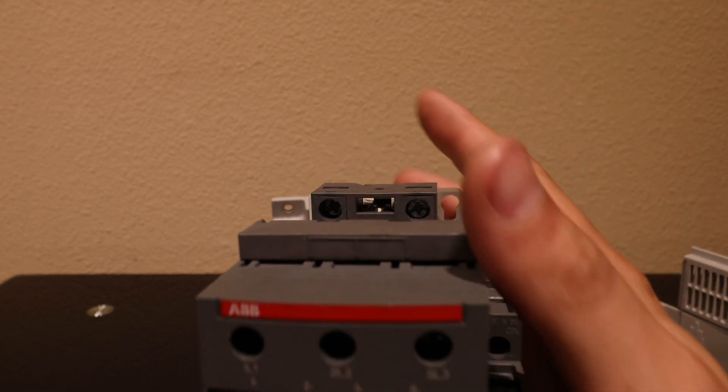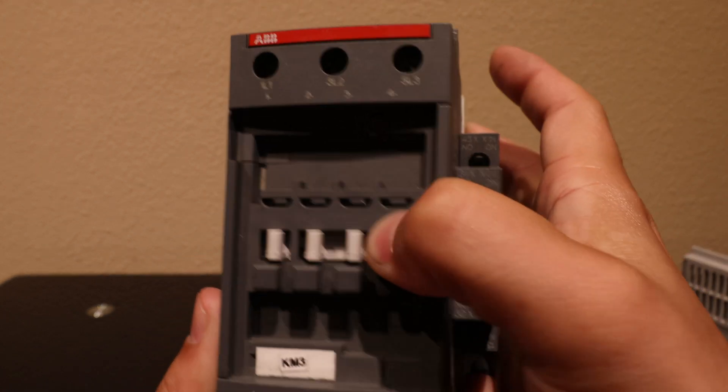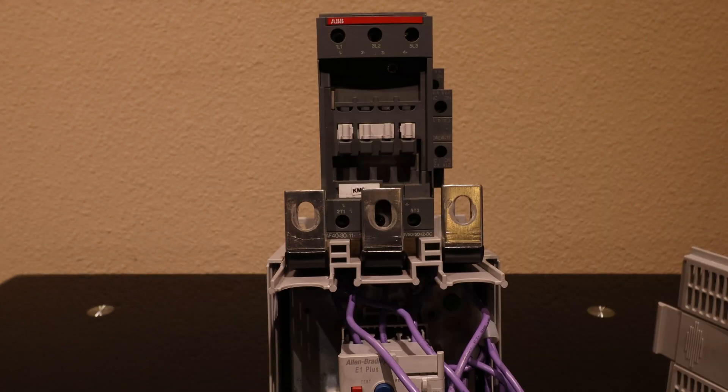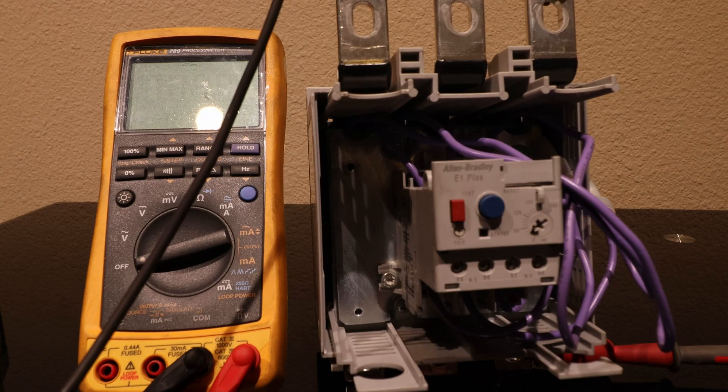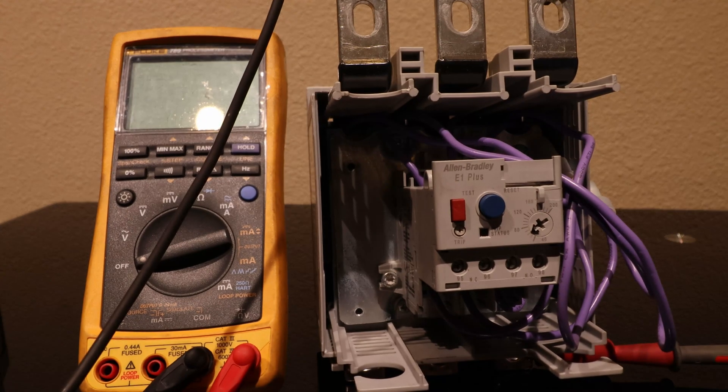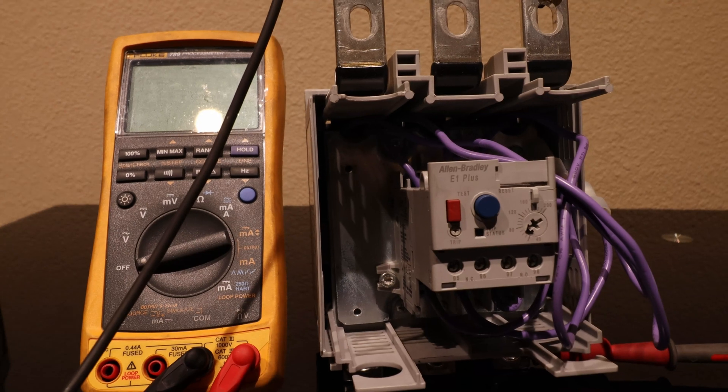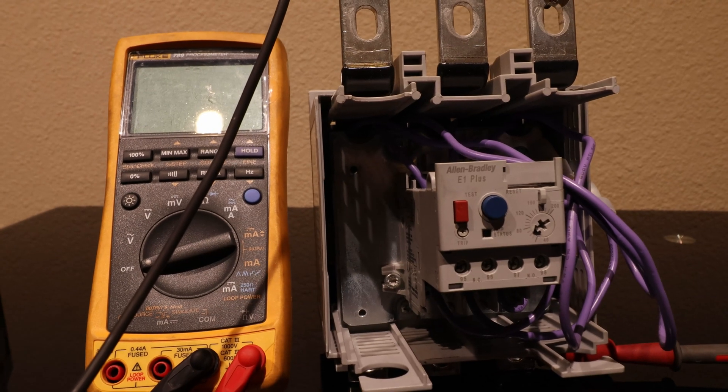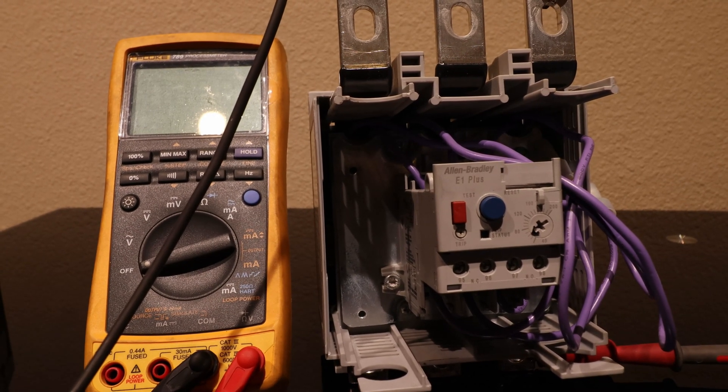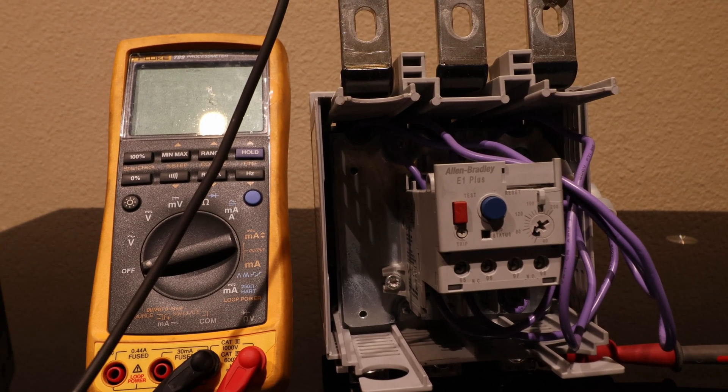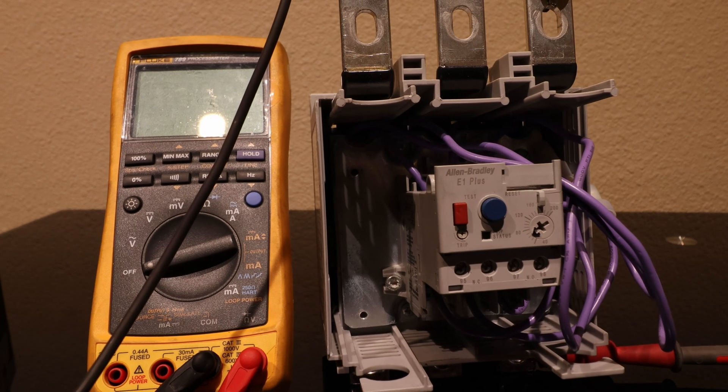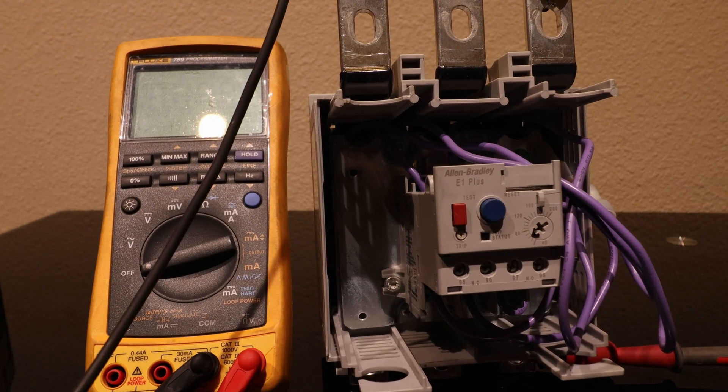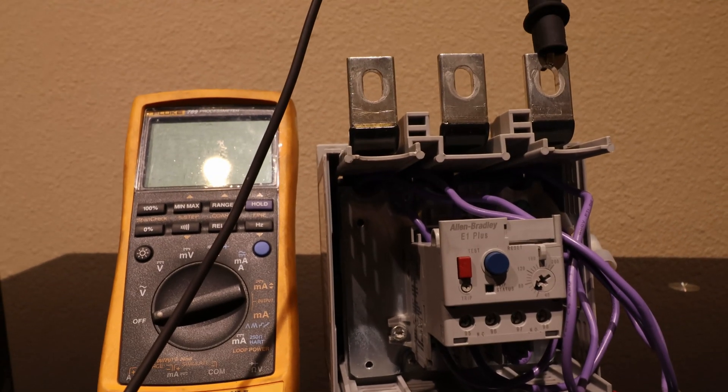This is the solenoid that would pull in the contact. We'll give you a real wiring example here in a second. I thought it would be worth mentioning to those who are new to this topic - the overload itself does not physically disconnect power to the motor or the load that it's protecting.